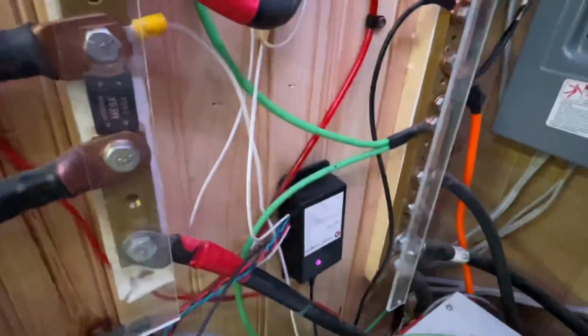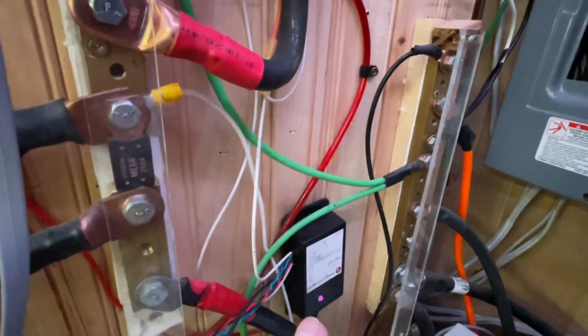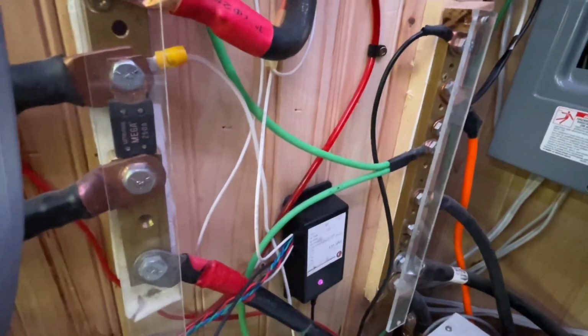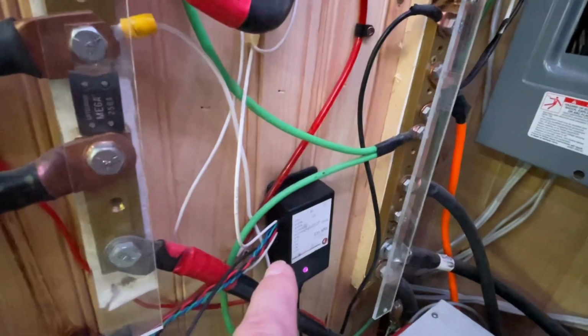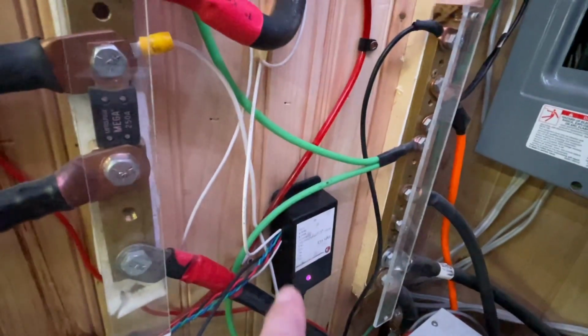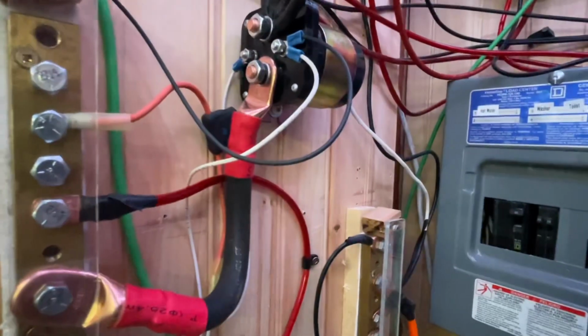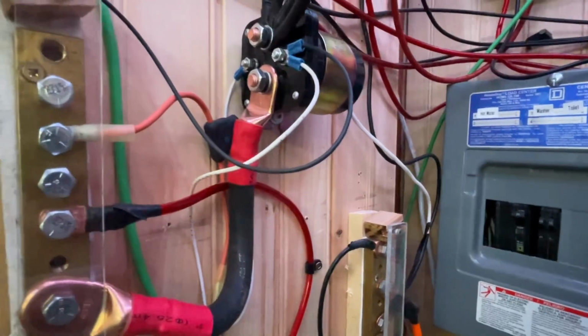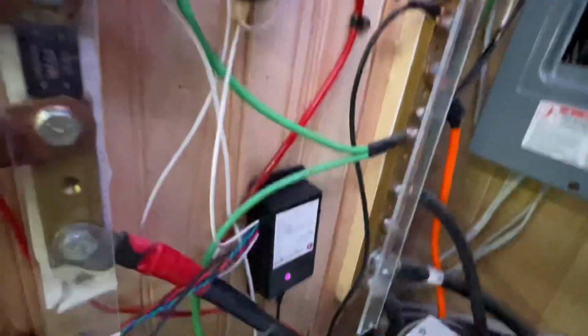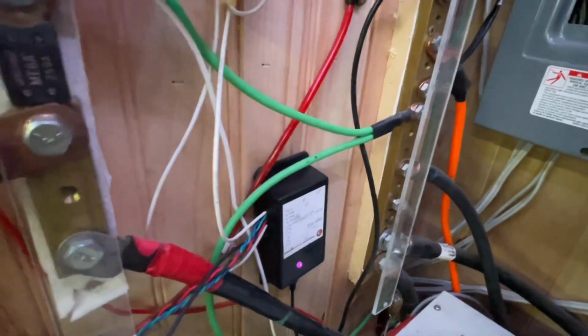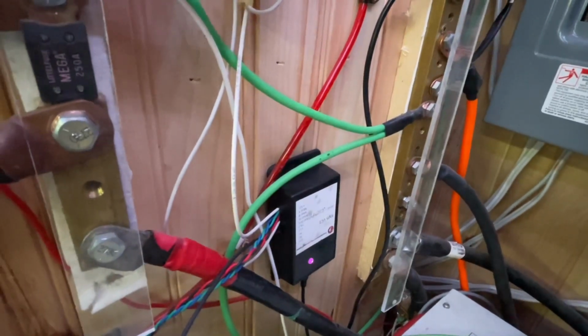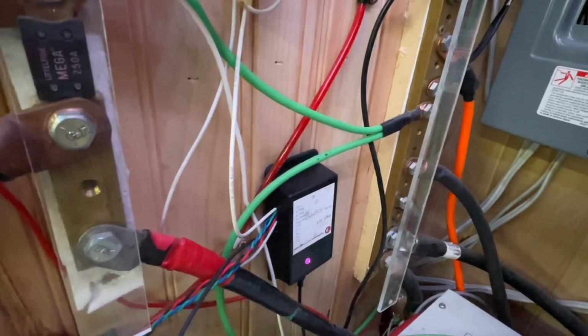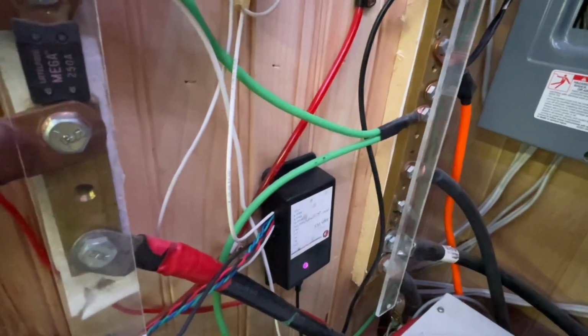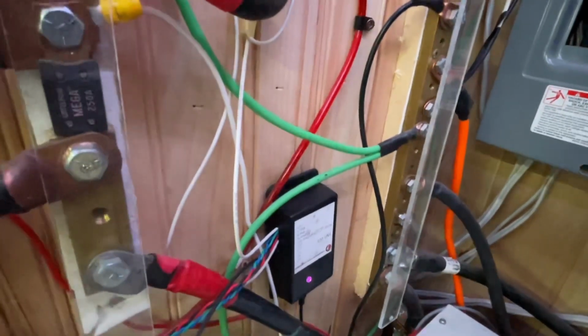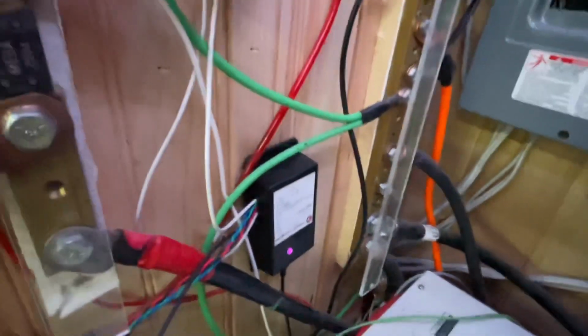When you first plug it in, it doesn't turn that relay on until you plug the computer in, and verify the configuration, then it will turn the relay on. It doesn't do anything prior to that. Once it's had power, it will go ahead and continue to function without the computer attached from that point forward. But if it loses power, you have to plug the computer back into it to make it happy.